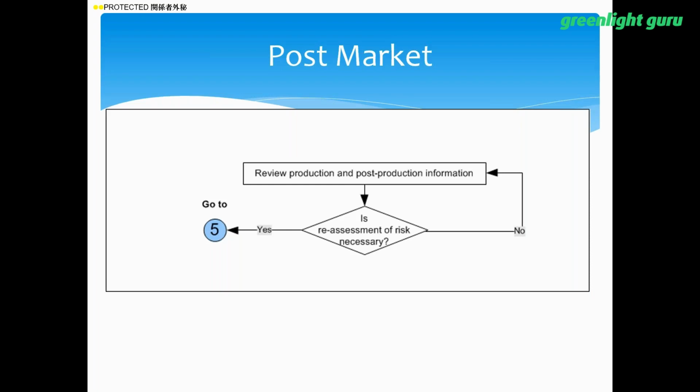But in the event you have to justify that, you will have documentation that shows that yes, you were aware of it, yes, you analyzed it, and yes, you made a conscious decision that the risk versus benefit was still valid. It doesn't happen very often, but it has happened in my career where we've gone to risk management board and found out that something did breach a threshold for a severity, not into a red zone and not into S5, but where we've seen with our continued use of the product that we did breach a threshold because we learned something new after the product was launched.